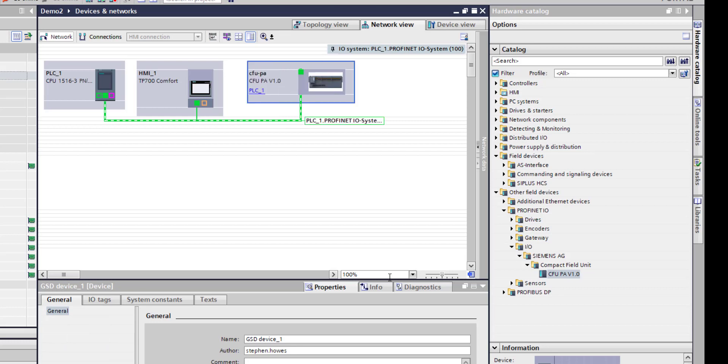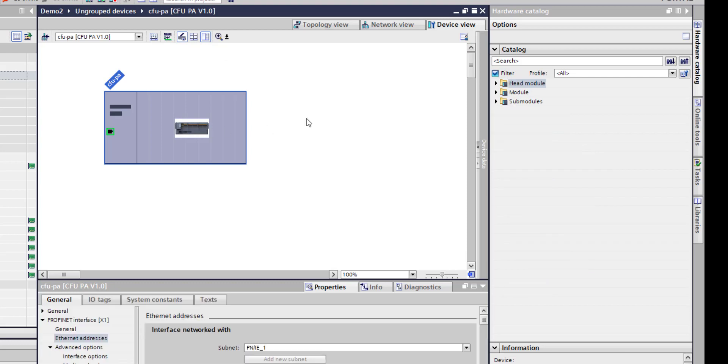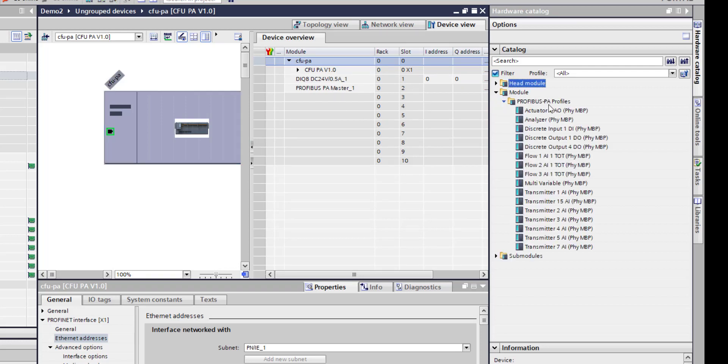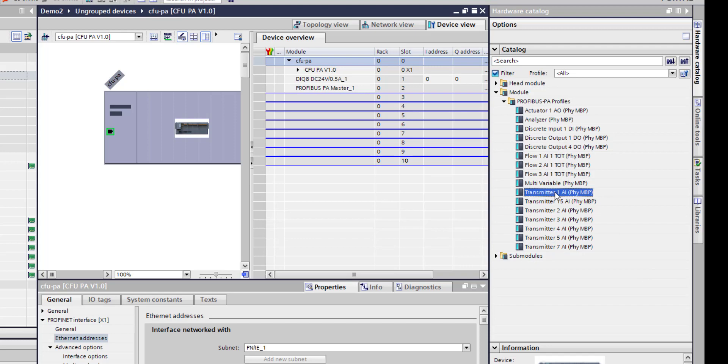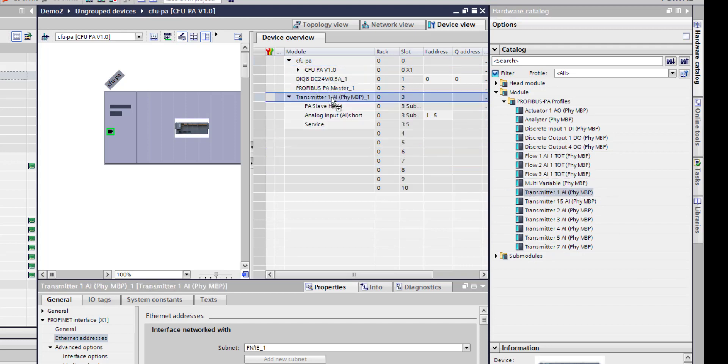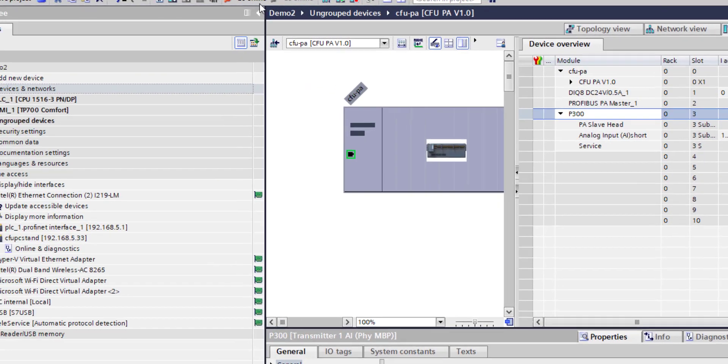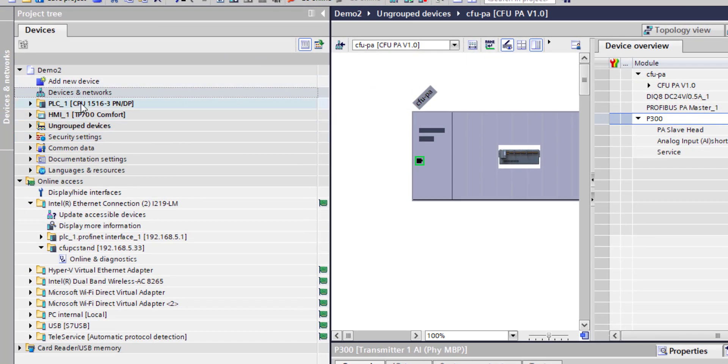I have my device. To add my instruments to it, I double-click. The tricky part is finding where your slot index table is - it's actually hidden here with this little button. If I expand it, if I go to Modules, PROFIBUS PA, we're connecting a P300 Siemens pressure transmitter which has one process value. If I drag that into the table, I can see this name here comes from this list - it's purely text. This is the name that will appear in your project and also on the display of the 1500 PLC when you start looking at the diagnostics.